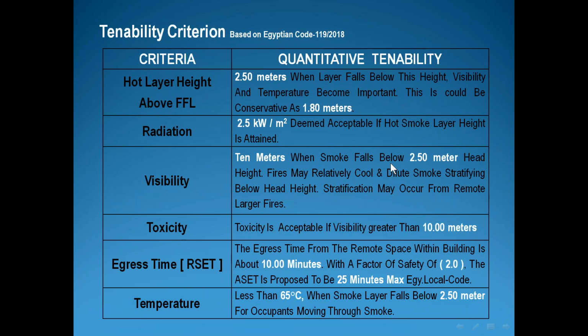When smoke falls below 2.5 meters, we are now moving with a smoke reservoir or smoke zone over the people, from 2.5 down to 1.8. Fires may be relatively cool, and dilute smoke may stratify below head height. Stratification may occur with remote, larger fires. This stratification normally appears if we have a huge fire load. Then the toxicity.